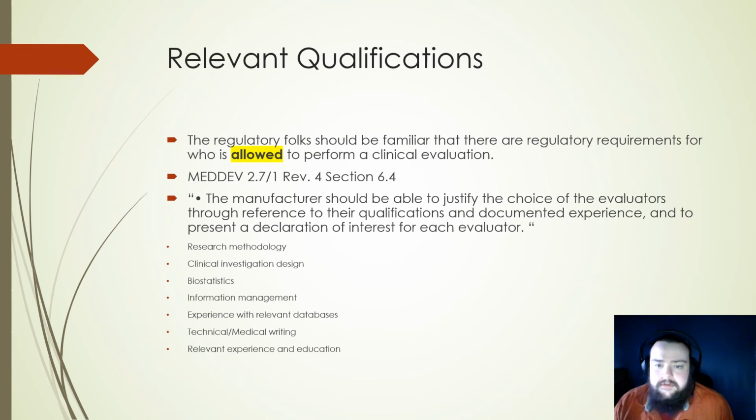And furthermore, there are actual standards out there for who you should allow anywhere near any portion of your clinical evaluation report. And specifically, as the manufacturer, if you're going to be compliant with MEDDEV 2.7/1 revision 4, specifically section 6.4, they state that the manufacturer should be able to justify who they picked.